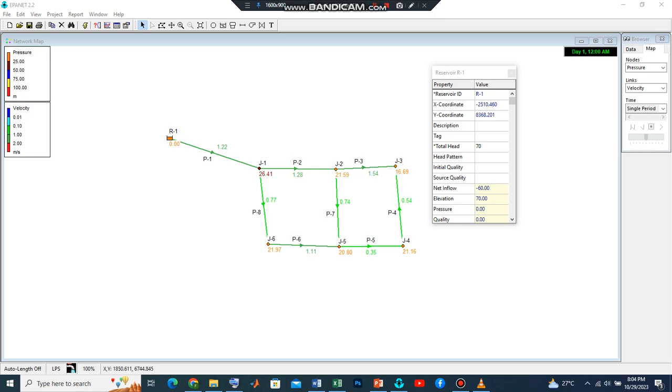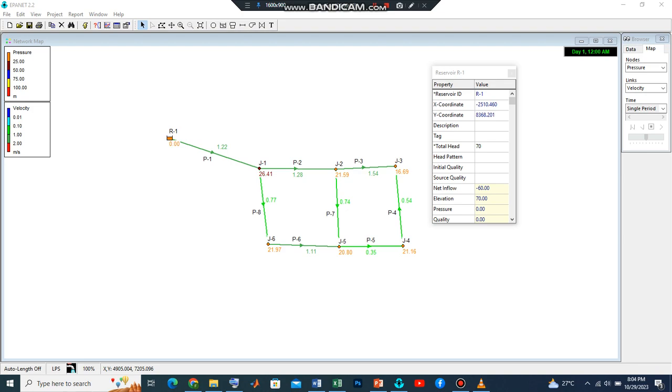Some of the parameters, especially the pipe sizes, have been adjusted and these values came up. There is actually a relationship between the formula for Darcy-Weisbach head loss, which states that your head loss is equal to the friction factor multiplied by L, which is the length of the pipe, multiplied by the square of velocity all over double the acceleration due to gravity, and also divided by the diameter.